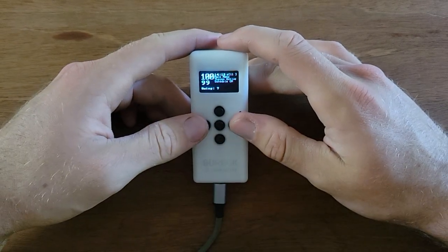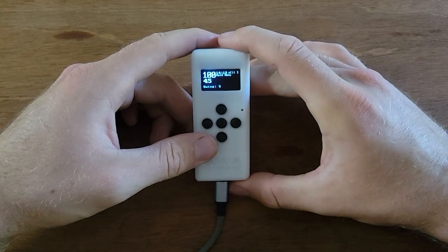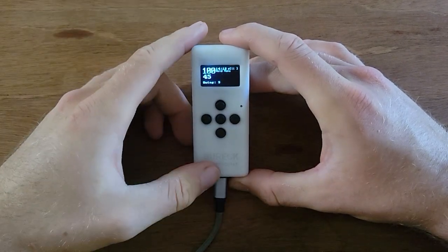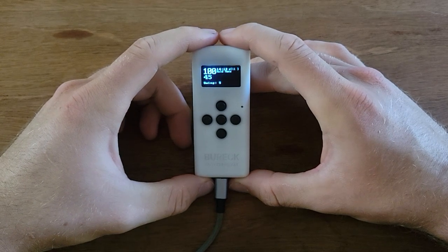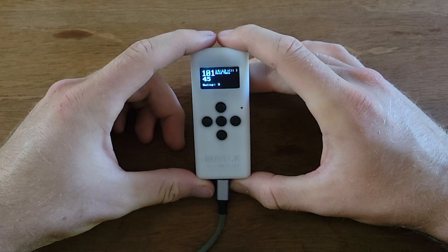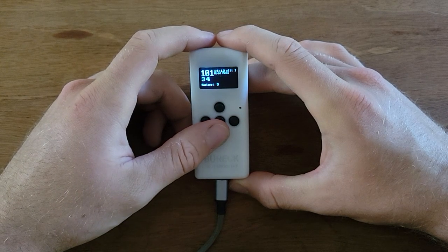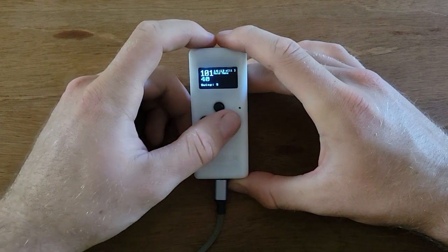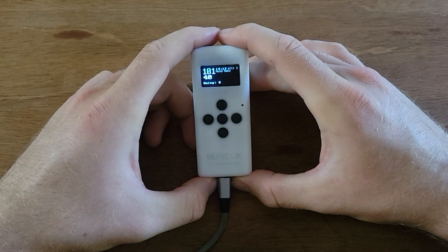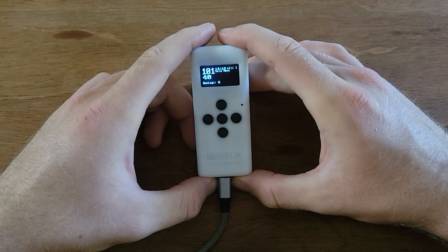So next, if we hit the right and the left buttons at the same time, we will enter the hold menu. The hold menu is a way to save some frequently used temperature and swing value that you want to go back to all the time. Common use for this would be if you have a pump house that you use as a garage maybe, or just a garage that has plumbing and you don't want anything to freeze in there. Every time you leave, you're going to be setting it down to probably something around 40 with a swing of 8. And you're going to want to do that every time you leave, and then every time you come back in, you're going to want to change it back to a comfortable temperature like 70.